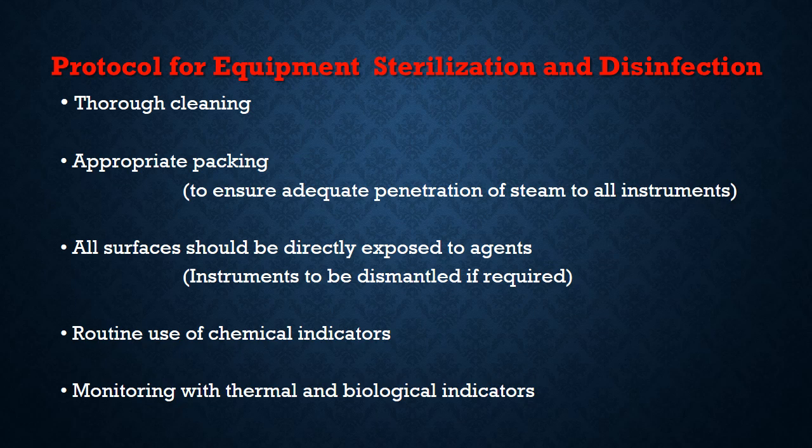So generally, the protocol or the method for equipment sterilization and disinfection would include the following steps. Instruments must first be thoroughly cleaned, and then packed appropriately to ensure adequate penetration of steam to all the instruments in that pack. All surfaces should be directly exposed to the agent, and certain instruments like laparoscopes may need to be dismantled.